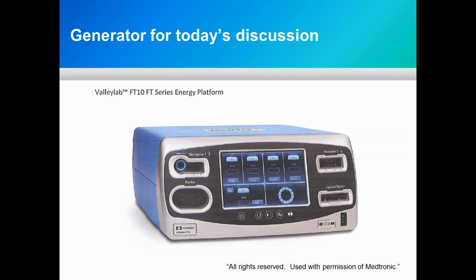Some pretty big changes in size and weight of this generator compared to the Triad. Roughly a 30% reduction in size and weight. And from a procedural perspective, it's 100 times faster than the Force Triad. So we're sensing density in tissue as the surgeon is doing a procedure. We're sensing changes in the tissue much, much faster. Again, 100 times faster, which to the patient is going to be pretty important.